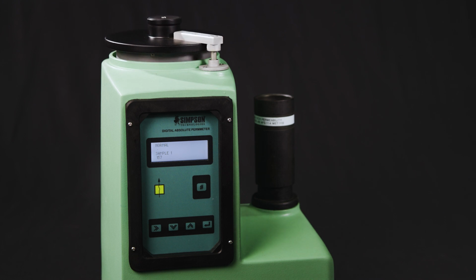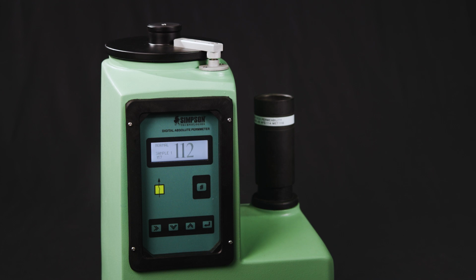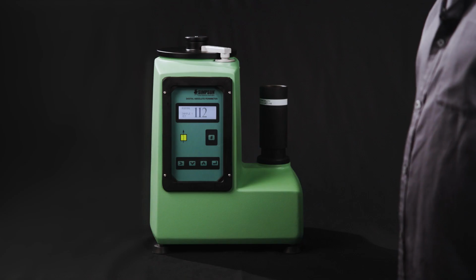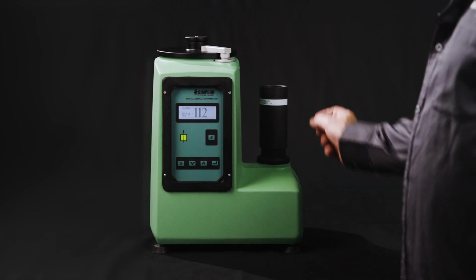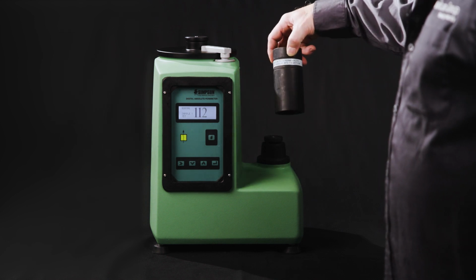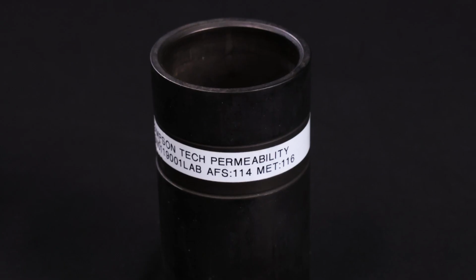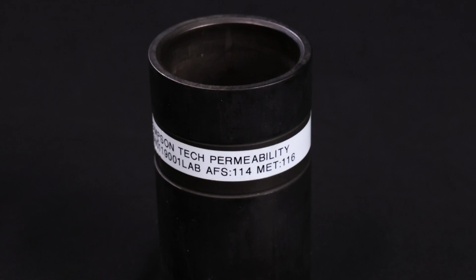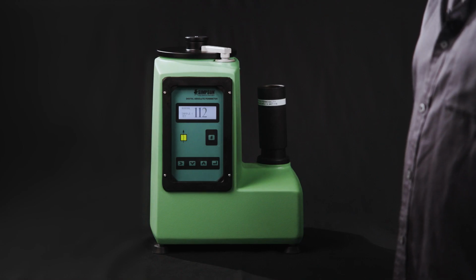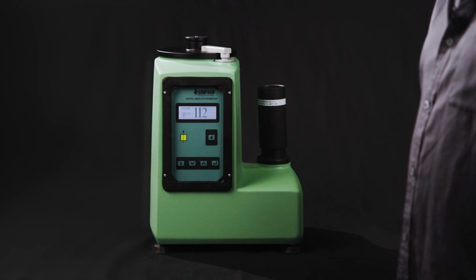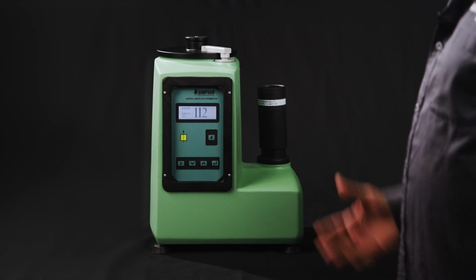And when the last dot disappears, then we'll get our permeability reading, which should be matched or very close to what we have on our permeability standard here. So this permeability standard was a 114. And we are at 112, which is within the plus or minus 5% for this machine. And that is it for the operational check on this machine.